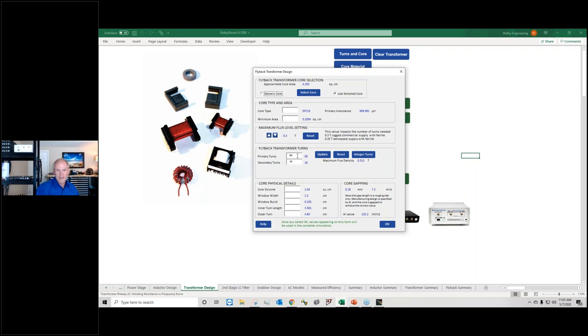Maximum flux density with this number of turns, you can see it wanted 90 turns, we put in 86. If I reset that, it will design right at 0.3 Tesla. If you start pushing the current limit in your converter, you'll see the Bmax going beyond that.